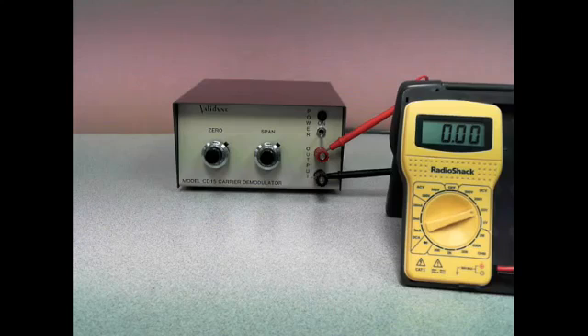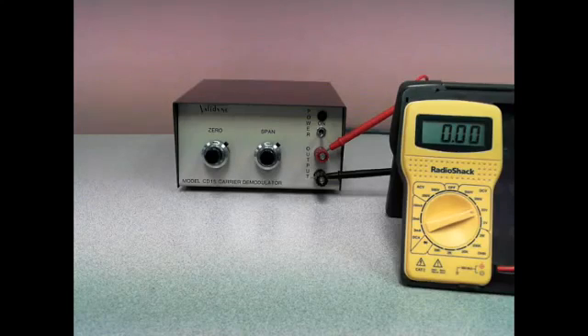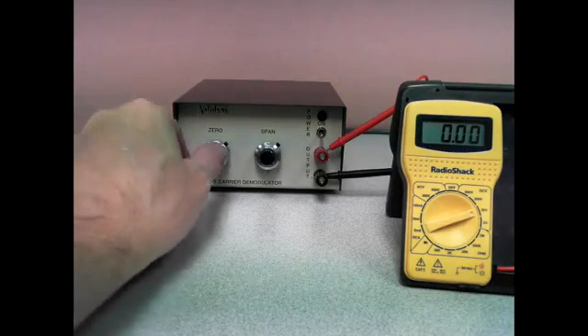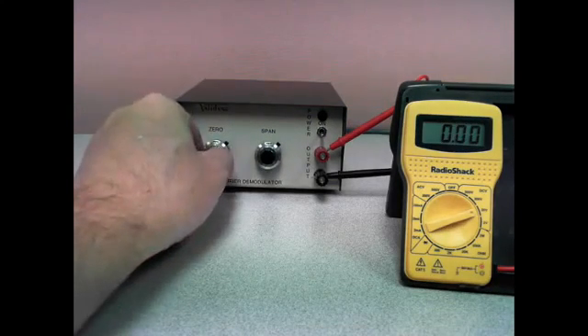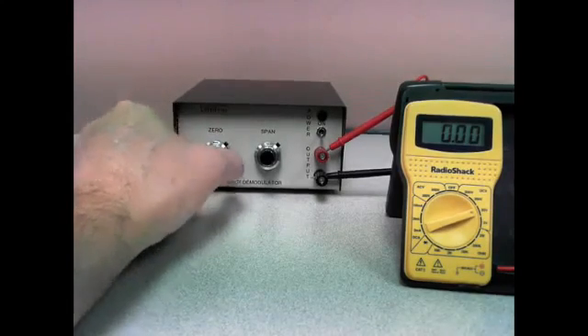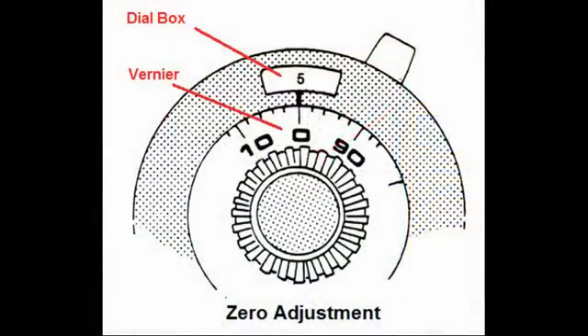Now we turn the zero adjustment such that the number five appears in the dial window. Next, turn the span adjustment until the number 10 appears in its dial window.